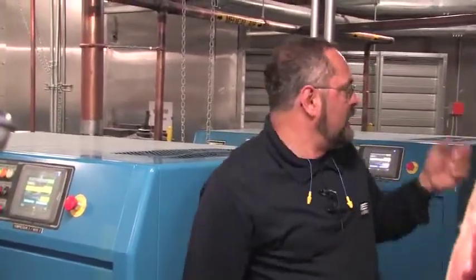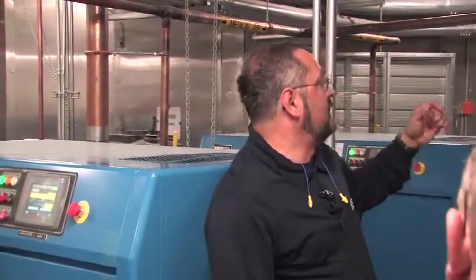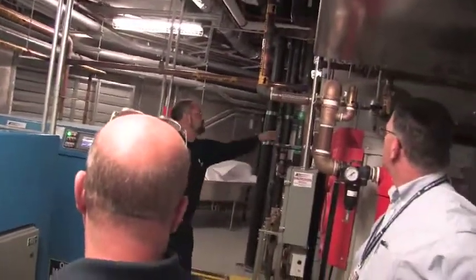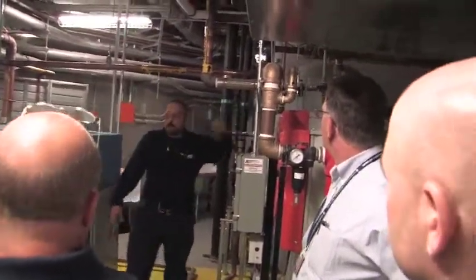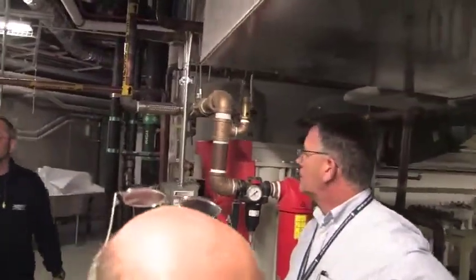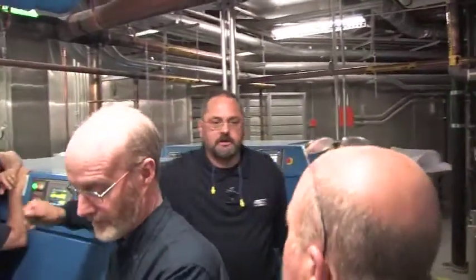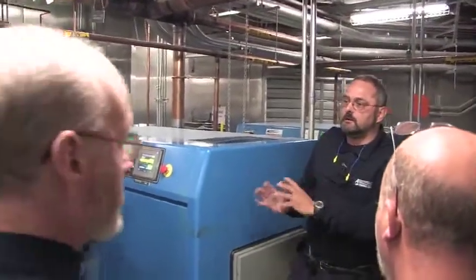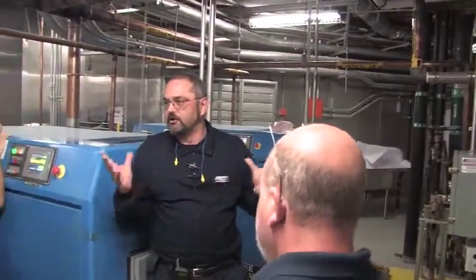So while it's really not in use yet, and there's no real consumption, the pressure changes are pretty much just when the dryer, by default, runs a purge cycle, or the drains on the tanks fire. And the pressure transducer, that's the other thing, is a master pressure transducer mounted in the pipe right here. That one is run back to this controller. It's the only one that's got the extra. They've all got their own internal pressure control. That one is operating the sequencer box. Call it a virtual sequencer box, but that's what it's doing.